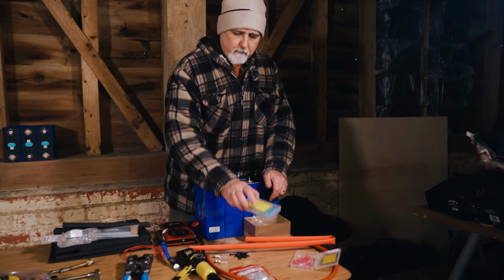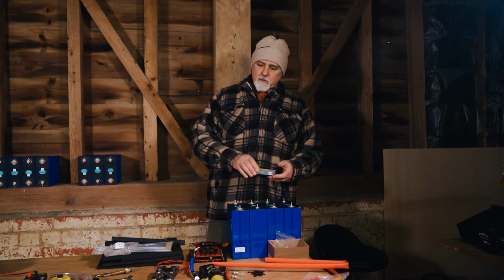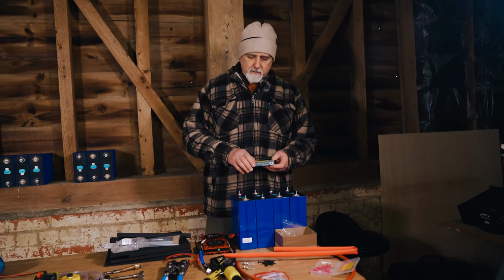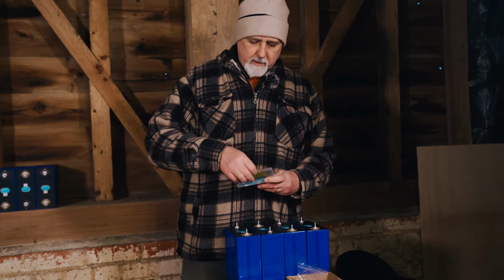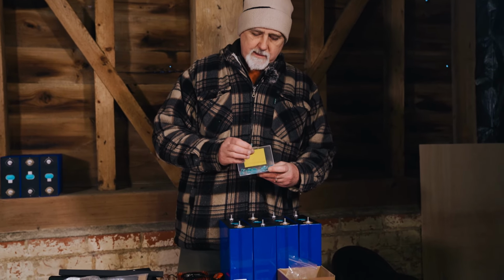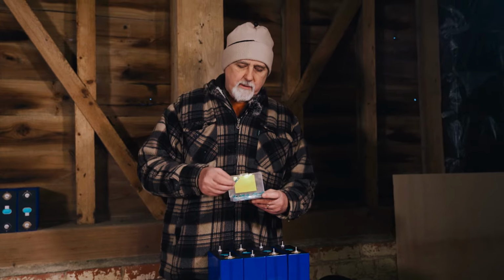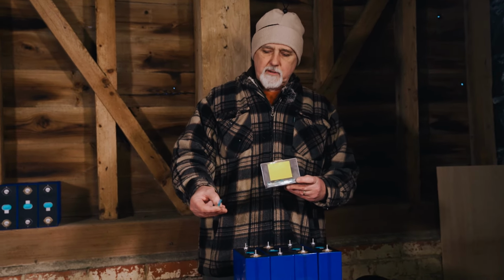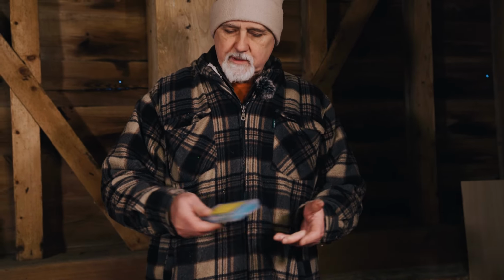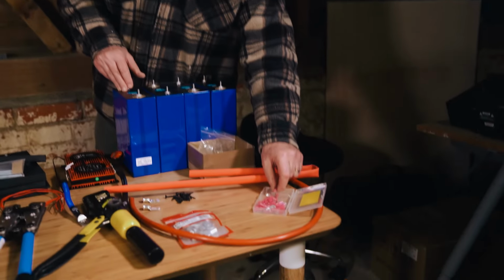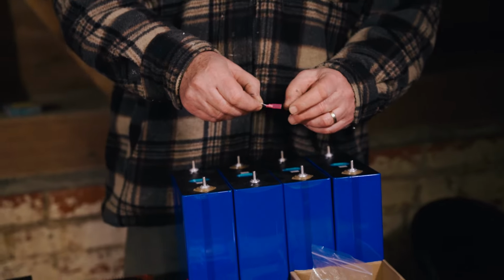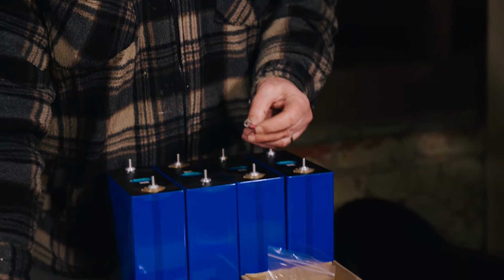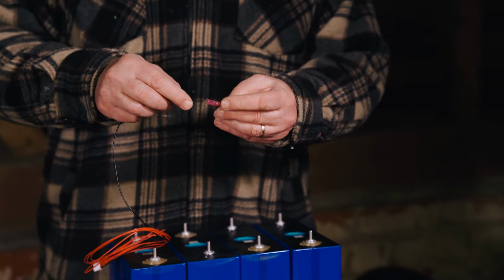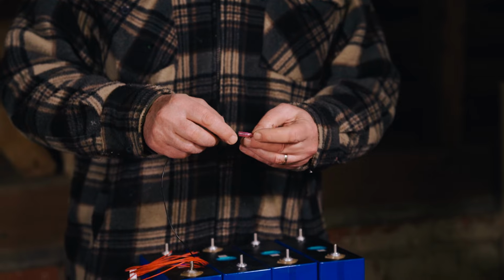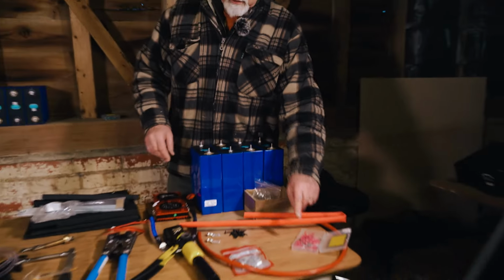I've shown you these blue because quite often you want to terminate the black one with the blue just to differentiate. But bear in mind the color actually denotes the size, and we don't think it's a good idea to have such a big hole that you then need to crimp closed. So we'd say don't bother getting these blue terminals - just stick with these, which are more pink than red I guess. Stick with five of these - you can't mistake this is the black lead, it's got a red or pink terminal on it, you just can't mistake it. That should be fine, so five of these is what you will need.